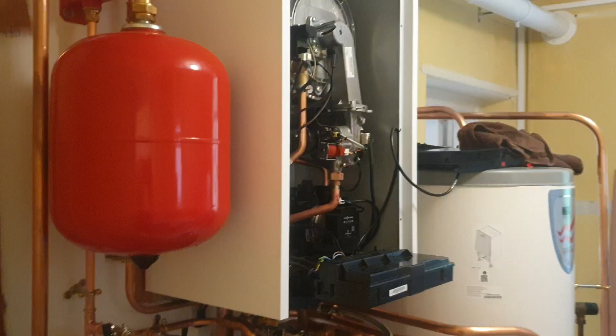Someone was asking about wiring on the Viessmann, so I thought I'd pick a not too complicated one. We've got two mixed circuits, an unmixed circuit, no secondary circulation pump for hot water, and the hot water cylinder is upstream of the plate heat exchangers. So I've got two mixer drivers, two mixer motors, two sensors, a cylinder sensor, and a pump.